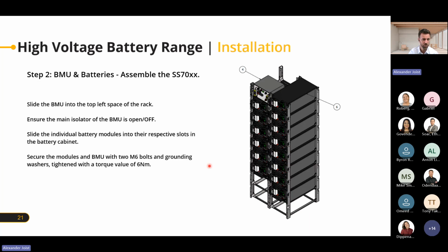Then the next step is you put the BMU in. It slides in on the top left, and then below on the right side you start with the batteries and slot in the high voltage batteries. Important: make sure everything is still switched off. Slide in all the individual batteries, then secure each module and BMU with the bolts and grounding washer provided, right away so they don't slip out or fall down. Make sure everything is secured.